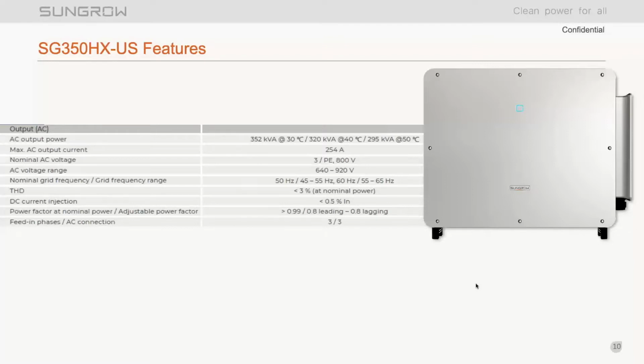The max AC output current is going to be 254 amps. Nominal AC voltage on the output is going to remain the same at 800 volts, three-phase with a PE. You can also land a neutral if the project requires it, or your transformer configuration requires the landing of a neutral. There are certain considerations for the PID mitigation that's in there. So with certain module types, if you're required to use anti-PID, then make sure to discuss with us or with CED Greentech the specific transformer configuration if you're going to be using the active anti-PID feature. And if you're not familiar with PID, let us know in the questions and we can go over that at the end.